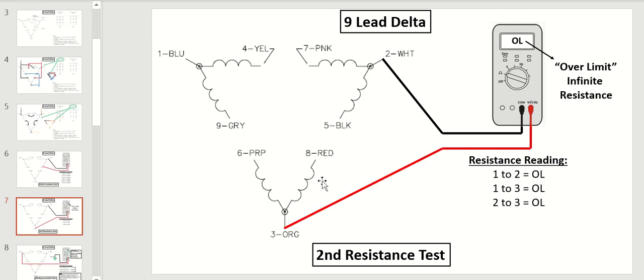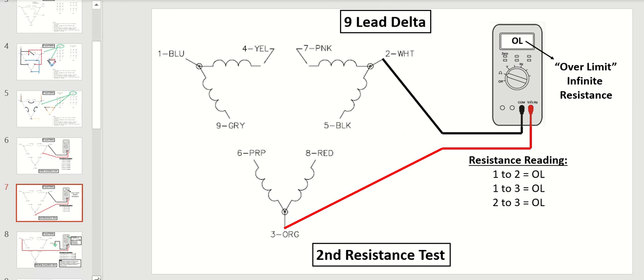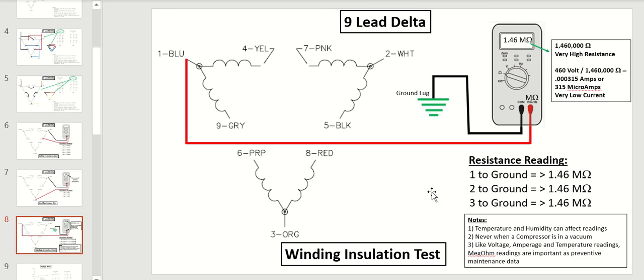The next test you want to do is to make sure that there's not a shorted connection between a set of windings. There should be no resistance or any type of connection between this winding, or this winding, or either one of these two. So if you take a resistance reading between wire number 1, 2, 2, 3, and 1, 3, you should have infinite resistance, and on your meter, it will say OL for over limit. And the last test to do is a megohm test, and now we're testing to see if the insulation on the windings is broken down. That could cause some damage to the motor.